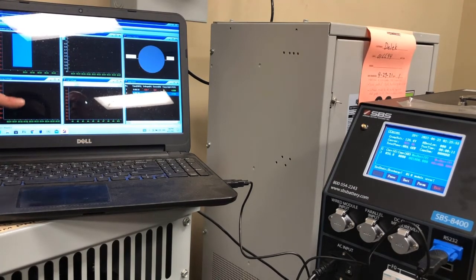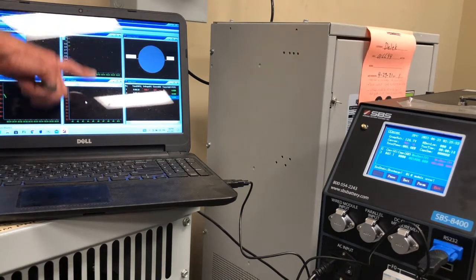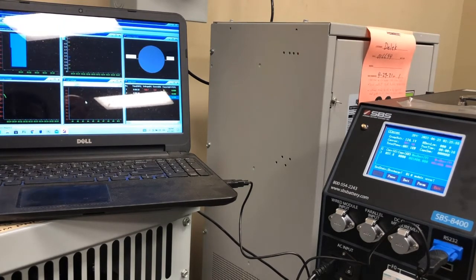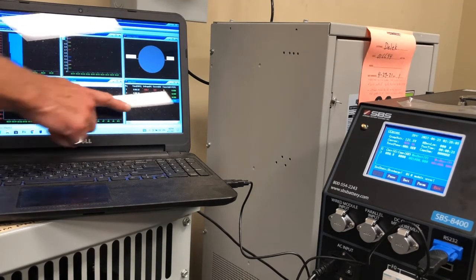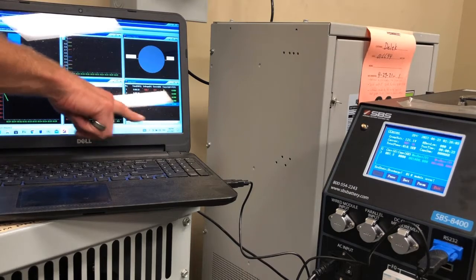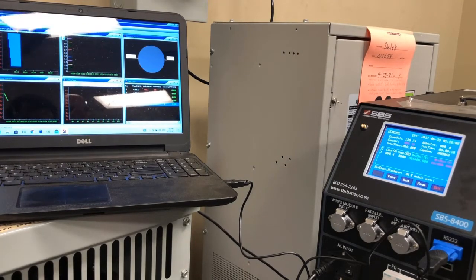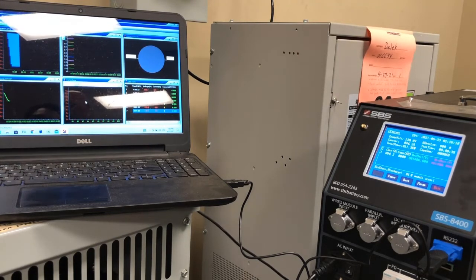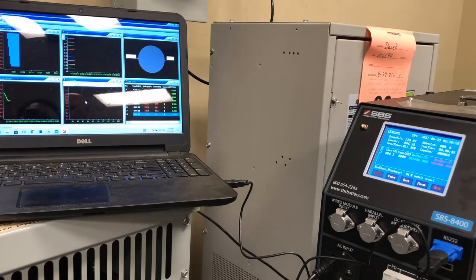Because I don't have individual monitoring voltages, I'm not going to see individual cells, but I'm going to see my overall group voltage, I'm going to see my overall discharge current, and I'm going to get my time stamps of my data every 6 seconds for the first 3 minutes, and then every 5 minutes that I set in the preset. And that's how you do real-time monitoring in conjunction with setting up and running a test on the 8400. You've got to set the software up to receive the data before you press the start button on the unit. Okay.